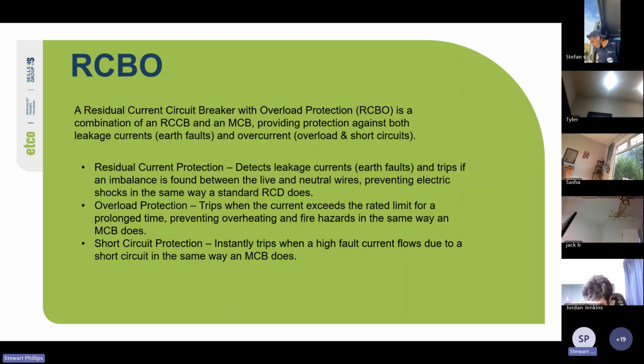So RC, residual current protection, detects leakage currents, earth faults, and trips if an imbalance is found between the live and neutral wires, preventing electric shocks in the same way an RCD or RCCB does. Overload protection trips when the current exceeds the rated limit for a prolonged time, preventing overheating and fire hazards in the same way an MCB does. And short circuit protection instantly trips when a high fault current flows due to a short circuit, in the exact same way an MCB would.